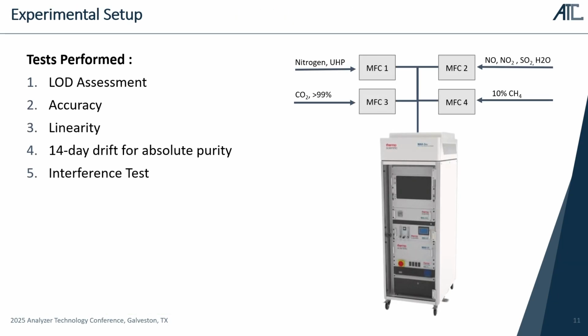So I'll get into the experimental setup a little bit. So the tests that were performed, we performed a limit of detection assessment. This was using the actual expected sample matrix, not just, say, CO2 or nitrogen. So we basically simulated a stream of greater than 95% CO2 and then greater than 0.3% methane to really show the capabilities of the quant regions. Next, we showed accuracy and linearity for NO, NO2, SO2, and CO2 itself from non-detect to a 10 ppm range, again in that diluted sample matrix.